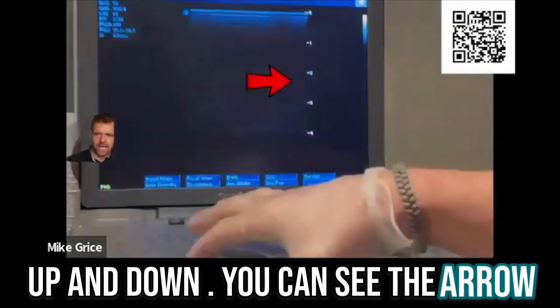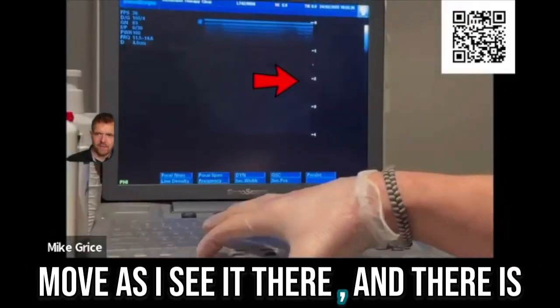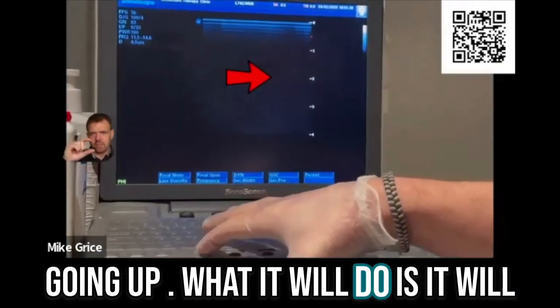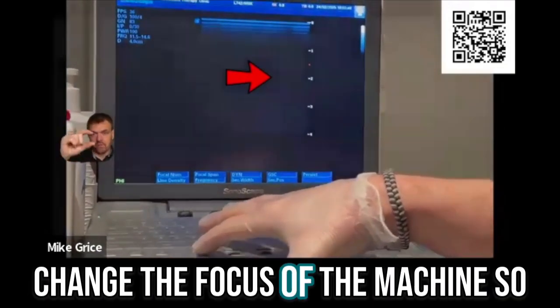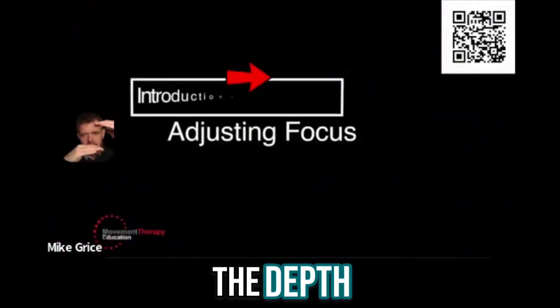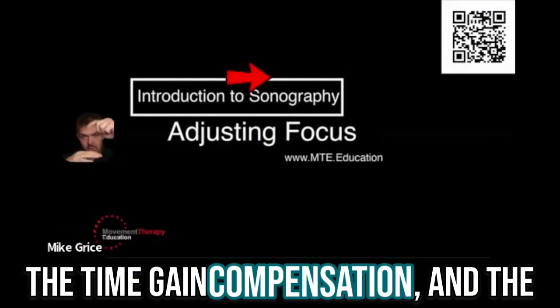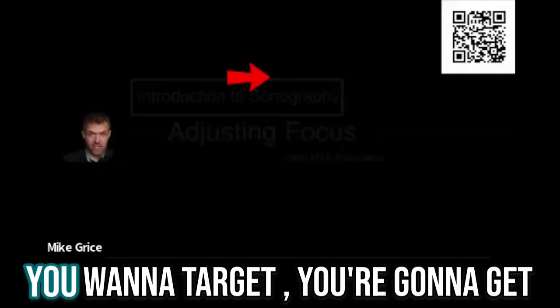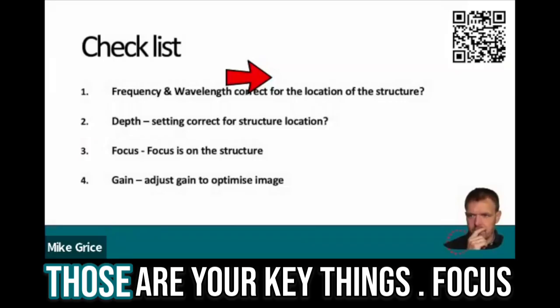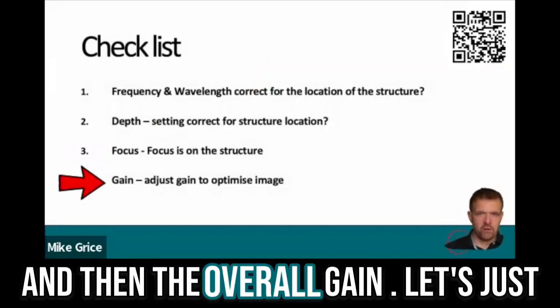So you can see the arrow move as I see it there, and there it's going up. What it will do is change the focus of the machine so it's higher or lower. If you change the depth, the time gain compensation, and the focal zone to the specific area that you want to target, you're going to get a really good image. Those are your key things: focus and then the overall gain.